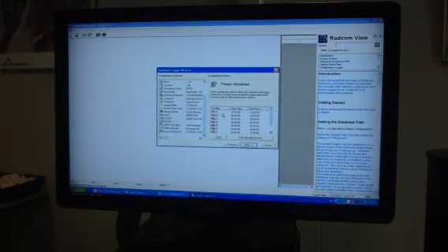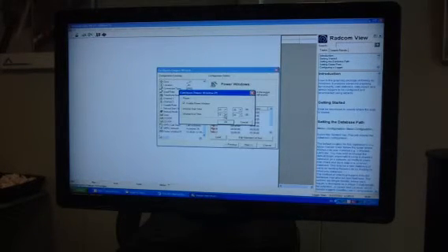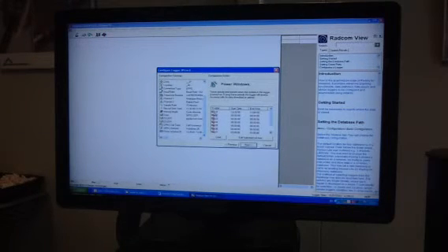Power windows: this is when you'll want the logger to wake up at a certain period of time. You can have a maximum of a 2-hour power window. You don't have to have a power window in one set time, you can split it up. So you double click on the power window, select the time you're interested in, and then make sure it's enabled, and then press OK. This takes the cross out, so you make sure that that is taken out and it's active again. Our standard multi-logs open up at 3 o'clock for 15 minutes, so the modems are working 15 minutes at 3 o'clock GMT.